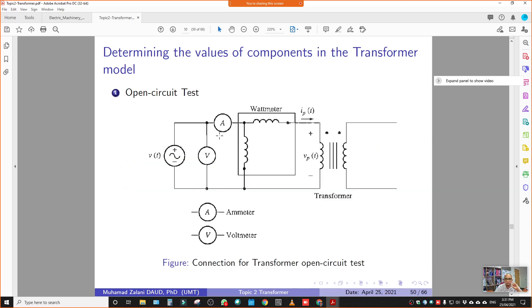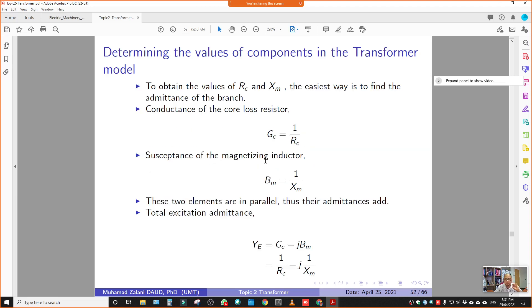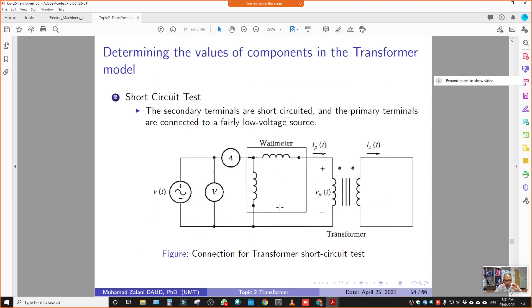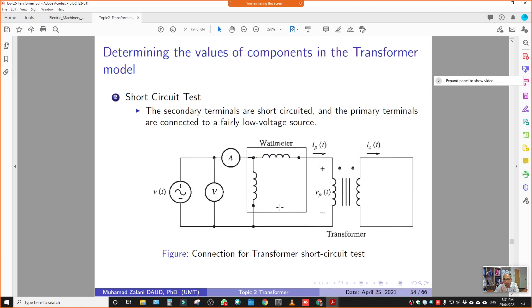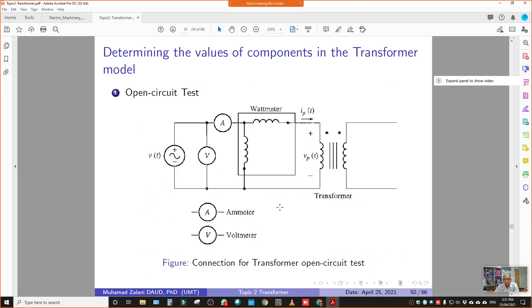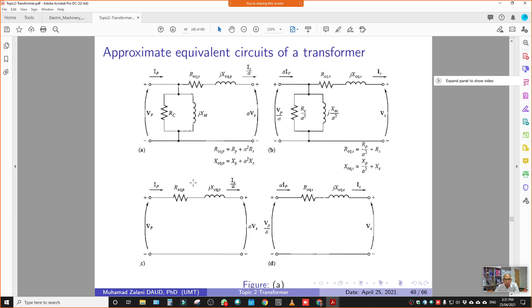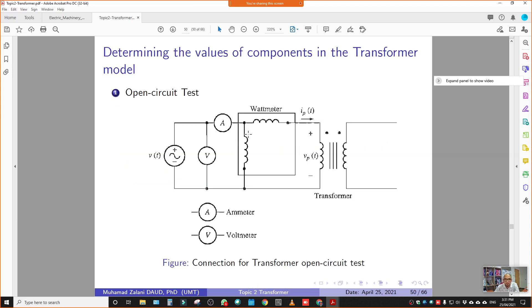In the open circuit test, we basically determine RC and XM — the excitation branch components. For the short circuit test, we want to determine the series branch components, REQ and XEQ. So to summarize: open circuit test determines the excitation branch values, and short circuit test determines the series component values.